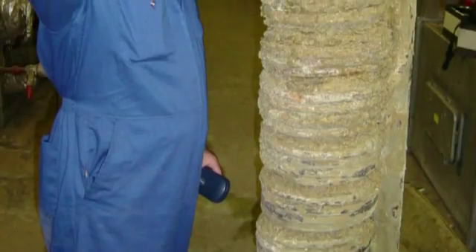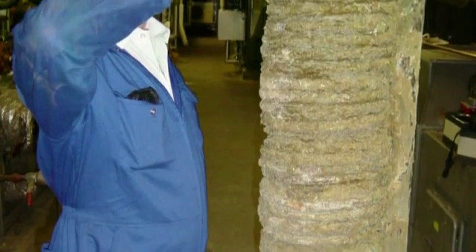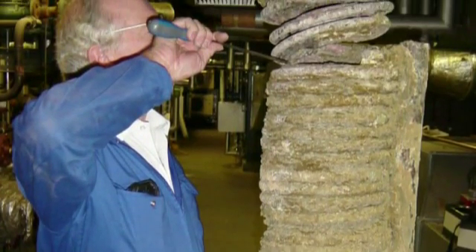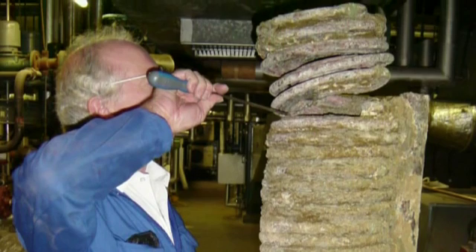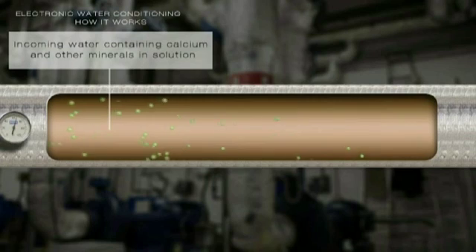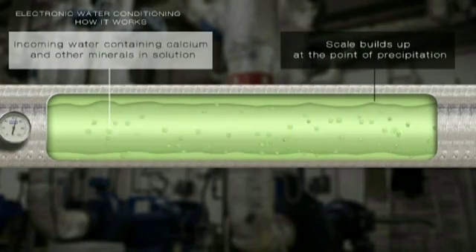In moderately hard water areas, it can take just 2 years for 6 millimeters of limescale to accumulate on pipework or heat exchangers, reducing heat transfer capacity by as much as 40%.